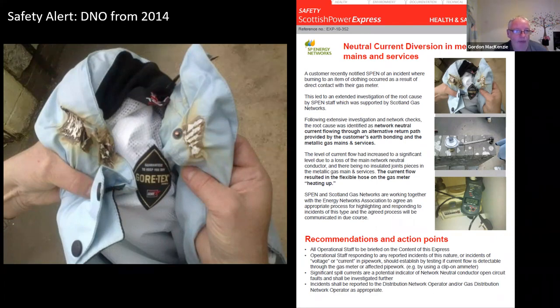And that network was operating 72 properties, we don't know for how long, without any network neutral whatsoever. And the current for the properties was using a cast iron gas main and the services for the property to breach through another section of houses onto a healthy neutral and return to the same substation on a separate LV. So we only became aware of it because of the level of temperature of the customer's jacket that was set on fire. It's a really interesting phenomenon I've been dealing with myself, but I like the recommendations and action points as well.